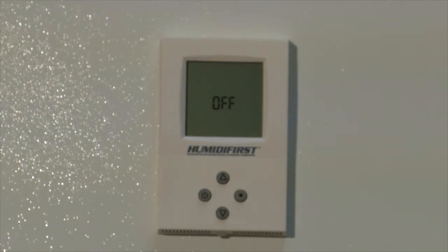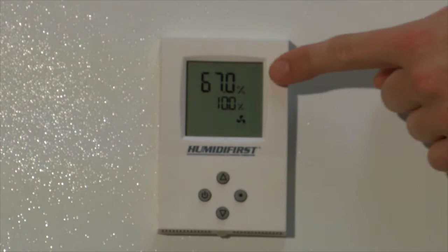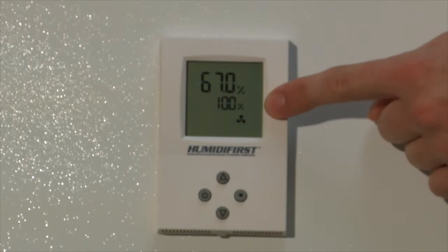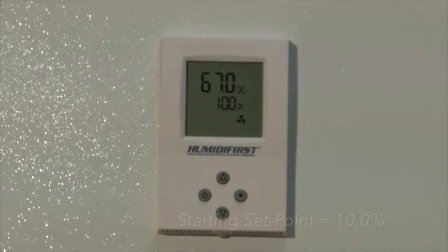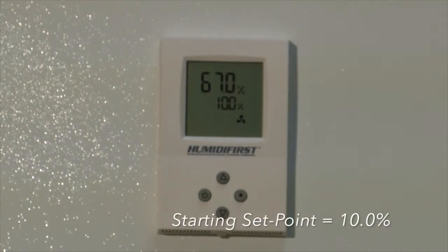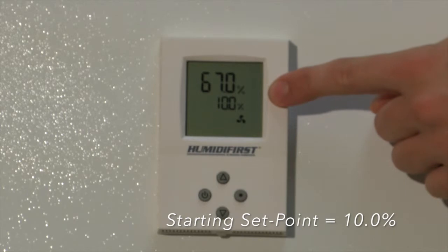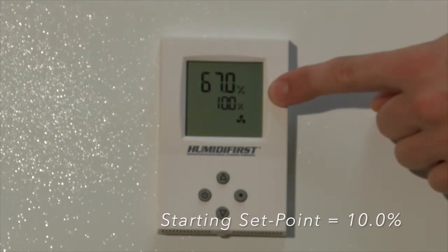The standard mist-free series ultrasonic humidifier comes with a front-mounted digital humidistat. This will show you the relative humidity in your space and your current desired relative humidity set point. To turn the humidistat on, simply press the power button. The large number on top is the current relative humidity in your space. The smaller number in the middle is your current set point. A new mist-free will ship with a set point of 10%. Note the decimal, as this can be mistaken for a set point of 100% relative humidity.